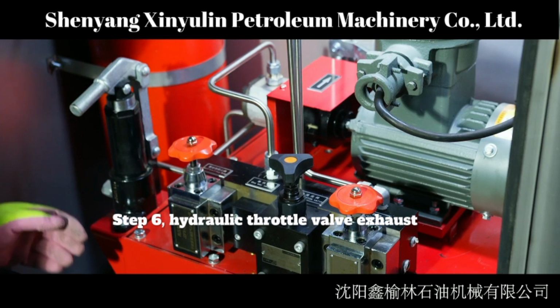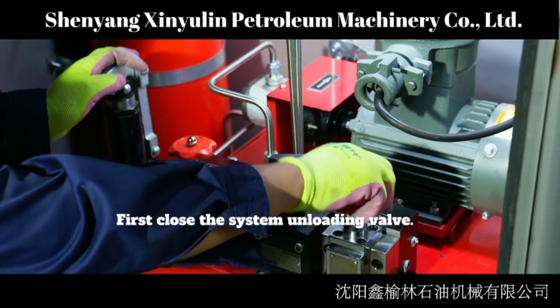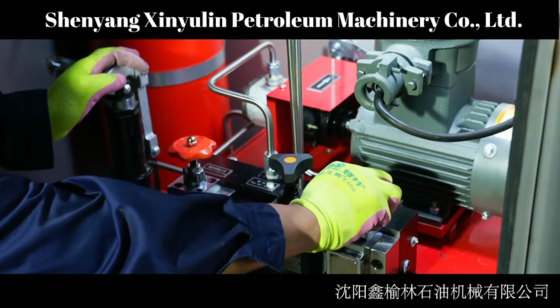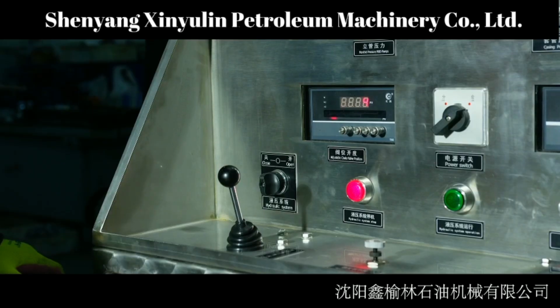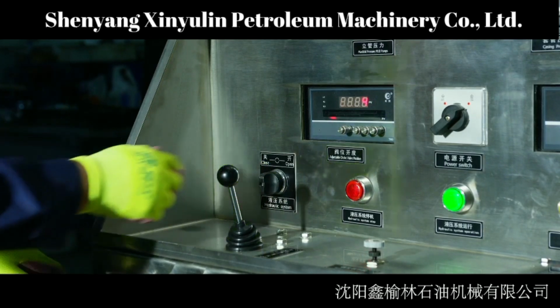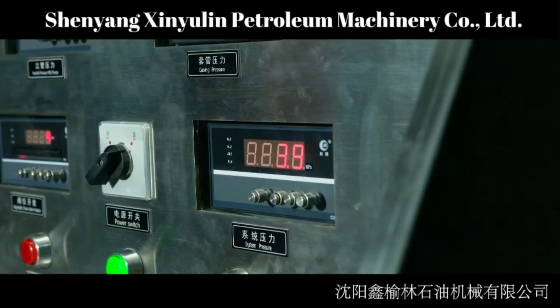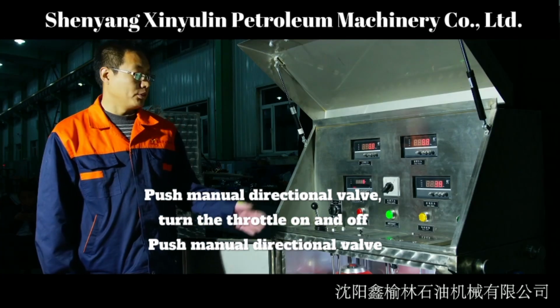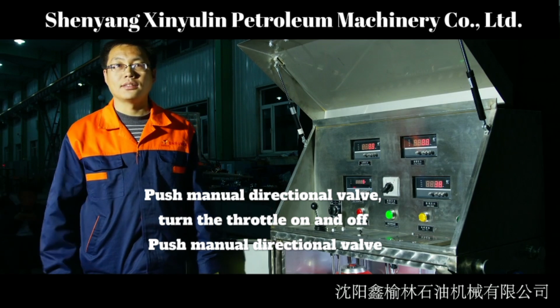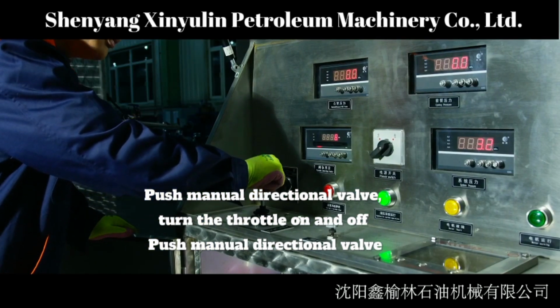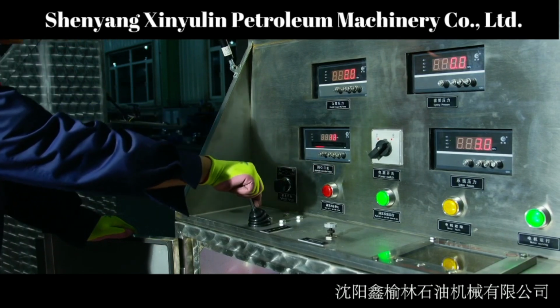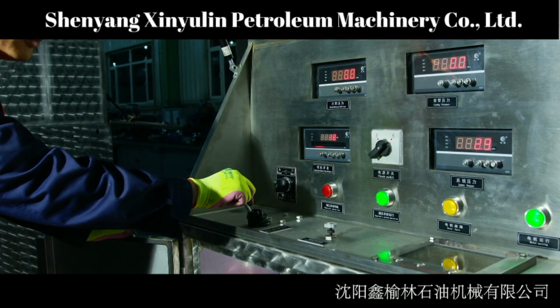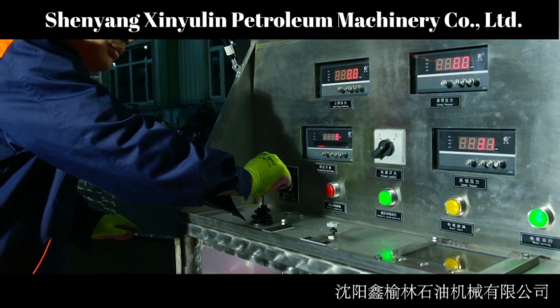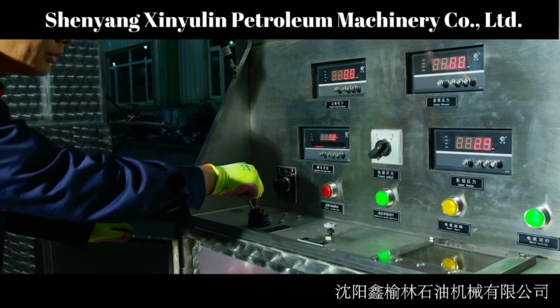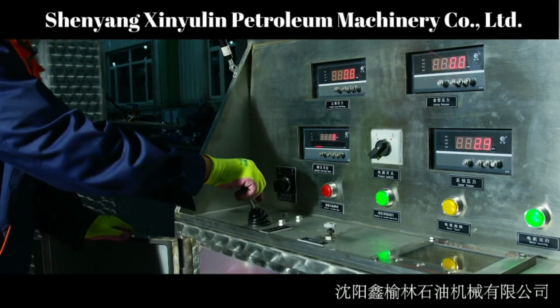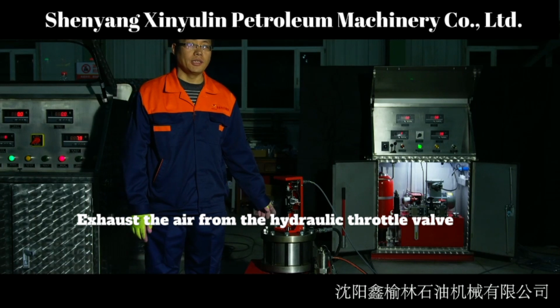Step 6. Hydraulic throttle valve exhaust. First, close the system unloading valve. Open the hydraulic system. When the system pressure reaches 4 MPa, the motor stops running. Push the manual directional valve. Turn the throttle on and off. Push the manual directional valve. Exhaust the air from the hydraulic throttle valve.